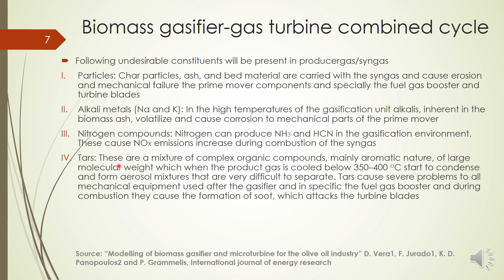The ash of biomass contains alkali materials — oxides of sodium, potassium, etc. — which cause corrosion of mechanical parts of the prime mover. If air is used for gasification, the large amount of nitrogen present can react with hydrogen to form ammonia, HCN, and other NOx emissions at high temperature, which must also be eliminated. Another important contaminant is tar — a mixture of complex, high-molecular-weight aromatic organic compounds. When the gas is cooled to between 350 and 400°C, tar starts to condense into liquid form and is very difficult to separate.